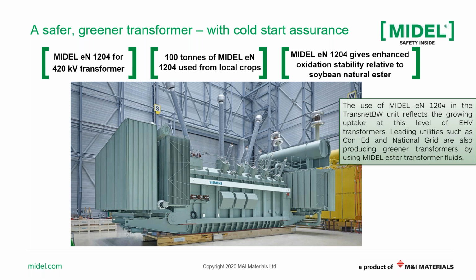This is a natural ester filled transformer, filled with our canola-based natural ester MIDEL EN1204. This transformer is a huge one, 420 kV, produced in 2019, very recent. This transformer used 100 tons of the liquid, made from local crops. The utility requesting this transformer required the use of a local harvest or local crop, and so they used MIDEL EN1204.